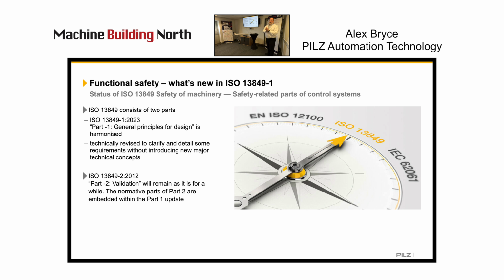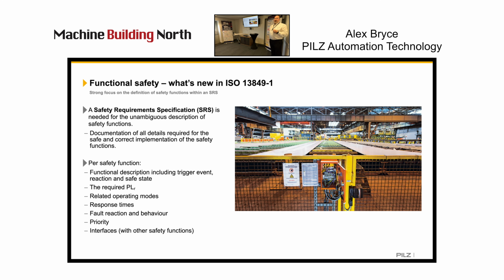13849, the safety rated control systems standard, also had a modification. Part 2, the validation bit, has now been embedded into part 1. It still has a standalone bit as part 2, but the requirements for validation and everything have been embedded, along with a definition now in the standard that you need to have a safety requirement specification.